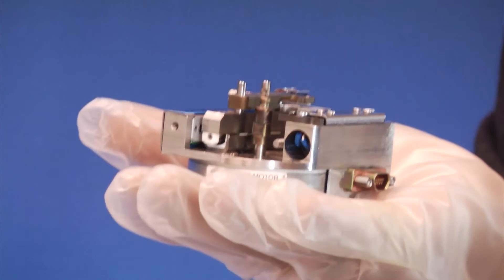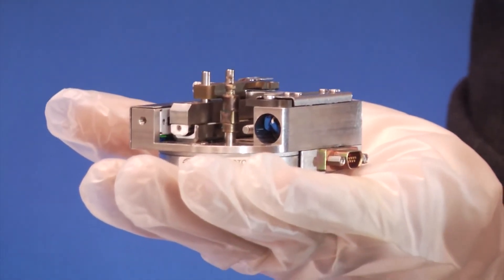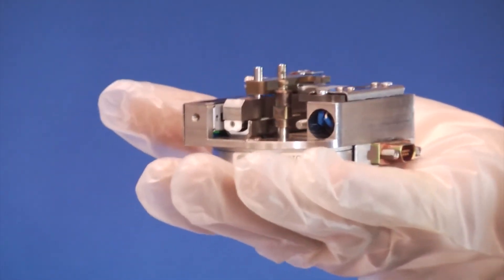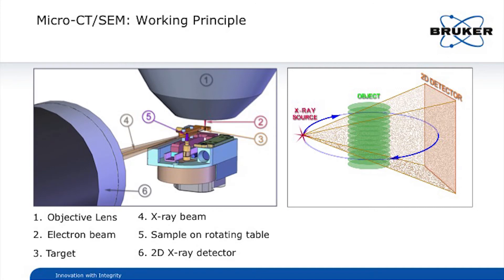Now I'm showing you the stage that you need for the microCT. This stage you can just put on your stage in the SEM and it has a rotating stub for the sample.